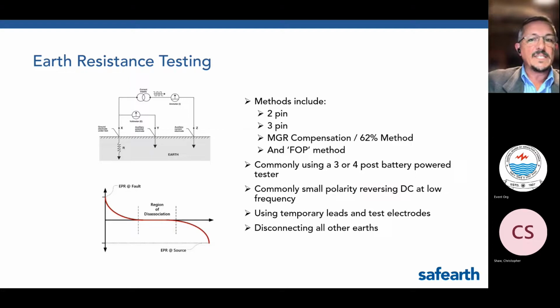This type of testing, earth resistance testing, has been relied upon for many decades, and it has its place. It can sometimes indicate condition. For example, a single electrode can be shown to be continuous. It can sometimes indicate performance. For example, where a prescribed electrode resistance is actually the output that you're after. For example, if it was a lightning design or a static ground and a nominated resistance was the required performance. There is wide held concern that this type of testing is often used and relied upon beyond its suitable uses and cases.